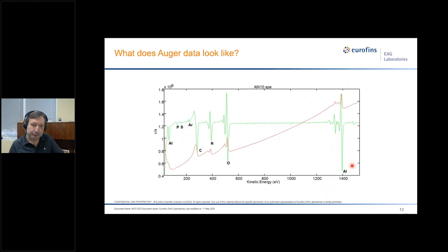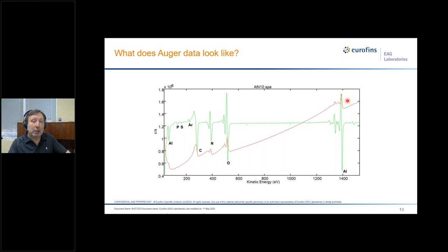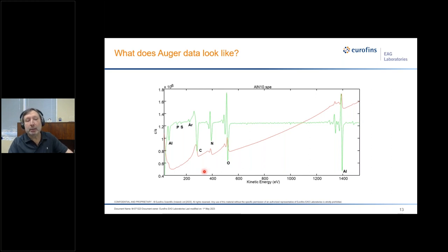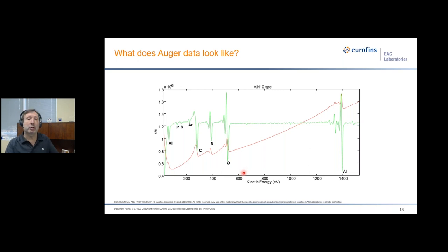By measuring the kinetic energy of the Auger electrons, it's possible to determine which element emitted it. We measure a spectrum, and there are a bunch of peaks, each corresponding to Auger electrons emitted from a different element. For example, if we see a peak at 275 eV, we know that came from carbon. By identifying peak positions, we can determine what elements are present on the surface. Additionally, by scaling intensities with sensitivity factors provided by the instrument manufacturer, we can provide a fairly decent estimate of the surface composition.